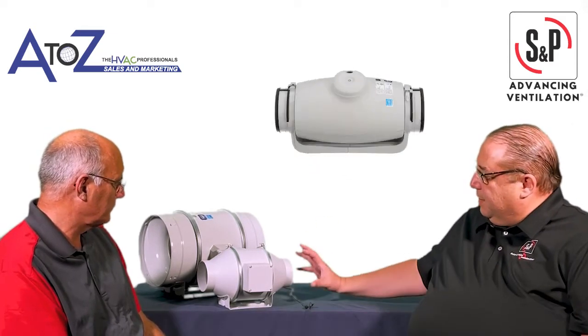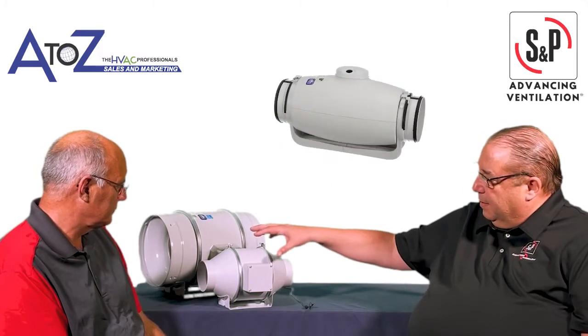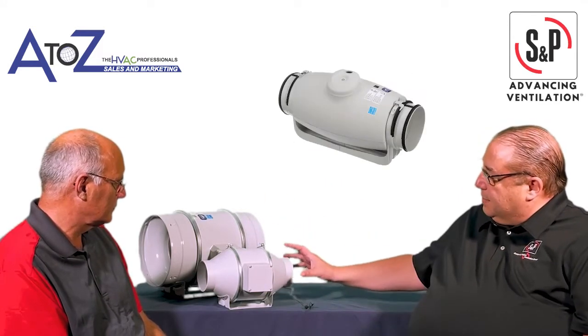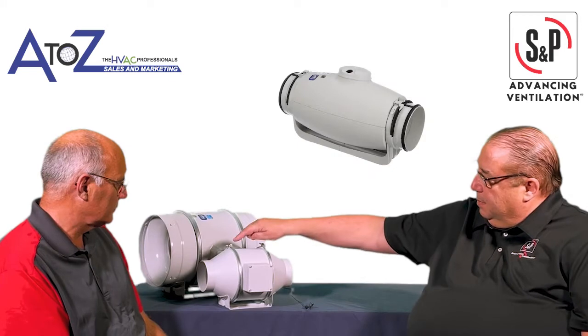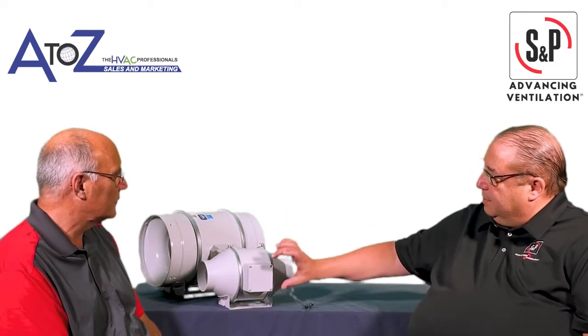They're very quiet, and it's the least expensive and easiest way to move air through round duct. You can put the round duct here, put the fan here, even put the round duct here, put these two clamps on, and then bring the motor with the fan in later, or swap it out while the casing stays in line. This adjustability makes it easier to install, to get to the electrical.